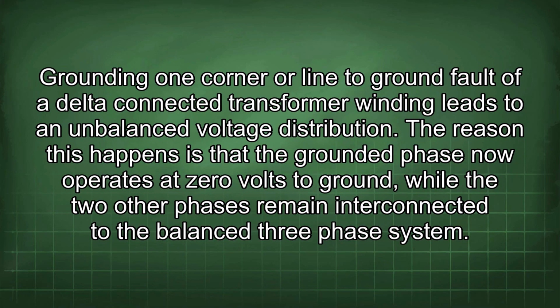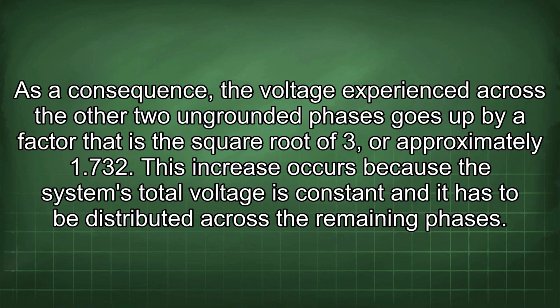Grounding one corner or line to ground fault of a delta-connected transformer winding leads to an unbalanced voltage distribution. The reason this happens is that the grounded phase now operates at 0 volts to ground, while the two other phases remain interconnected to the balanced three-phase system. As a consequence, the voltage experienced across the other two ungrounded phases goes up by a factor that is the square root of 3, or approximately 1.732.